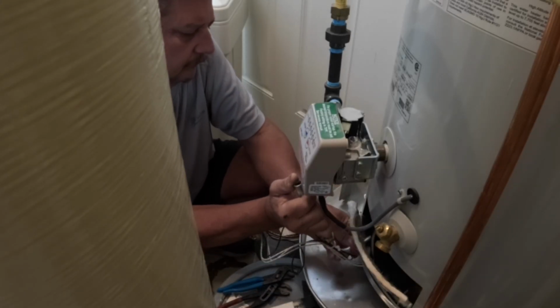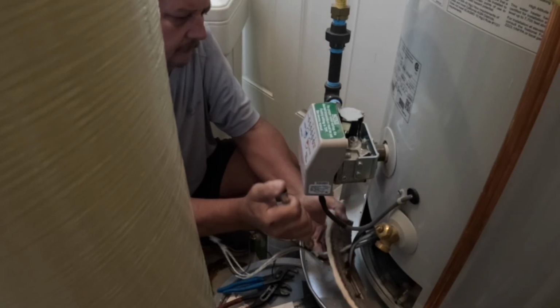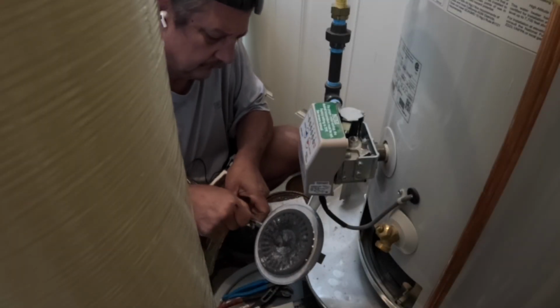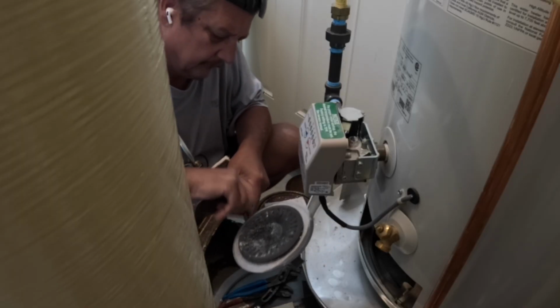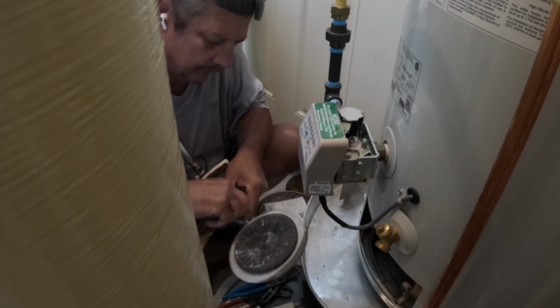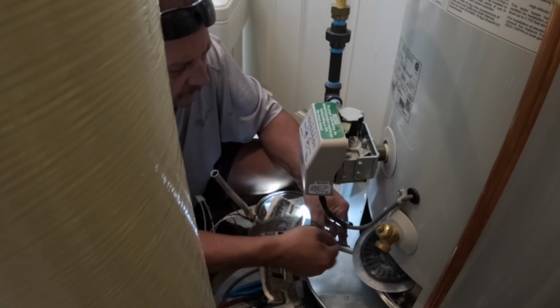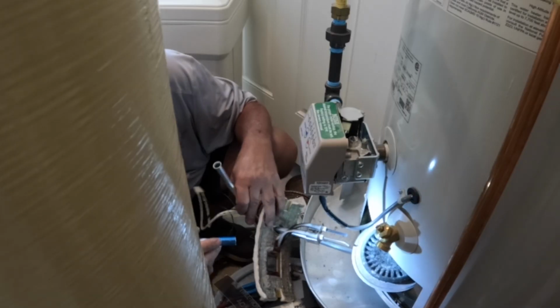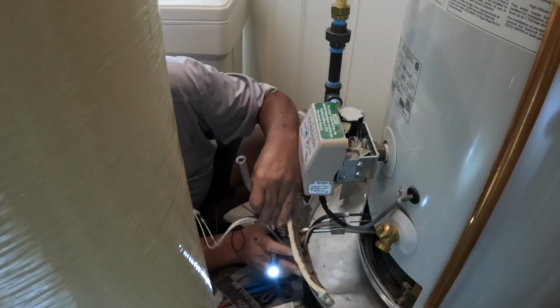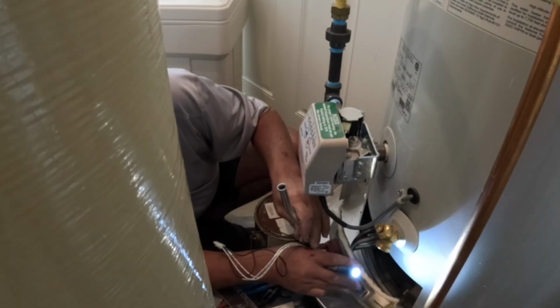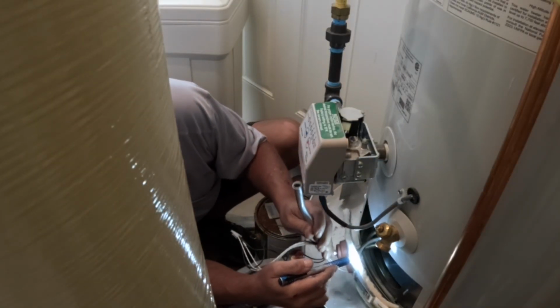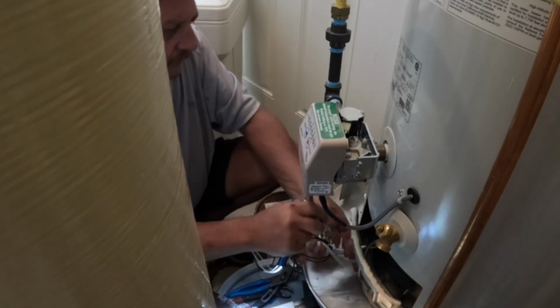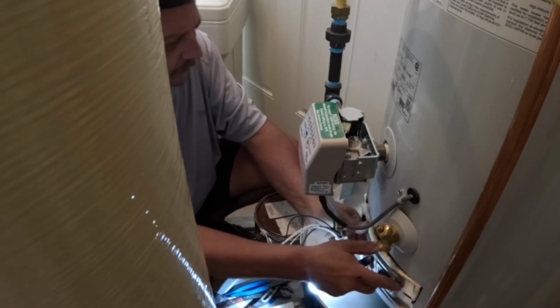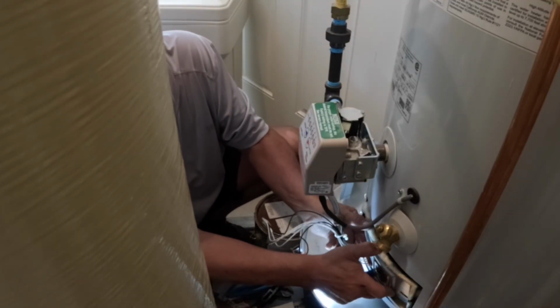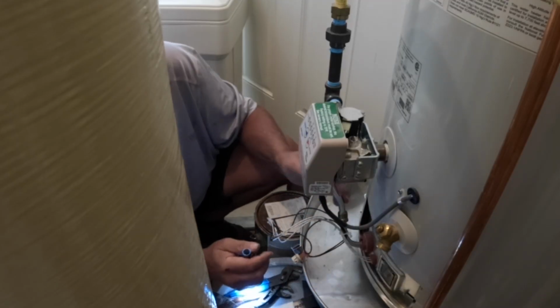Most water heaters have some sort of a stand either on the bottom of the burner assembly or made into the bottom of the water heater that supports the burner assembly. And all I'm using here, now that I've got it out, is some light sandpaper, just lightly cleaning the flame sensor. It's the metal probe next to the pilot assembly. And we just want to clean the debris off of it just a little bit. It won't look very bad, but every little bit that's on there acts as an insulator against that flame. So when that flame is running, it's insulating it from the sensor, not allowing the sensor to read the heat accurately. And the water heater only knows one thing to do when it doesn't sense that flame, or doesn't sense X amount of flame, is shut off.